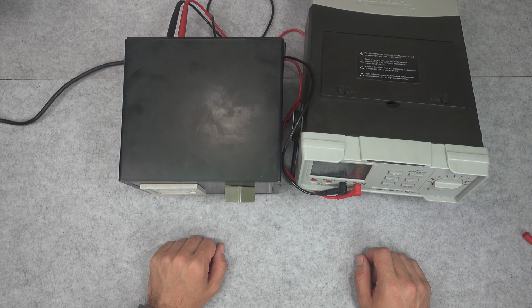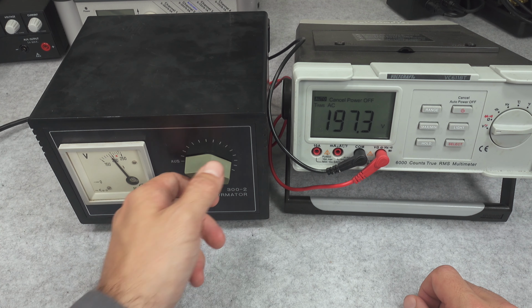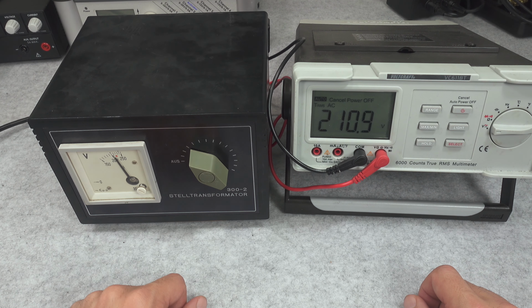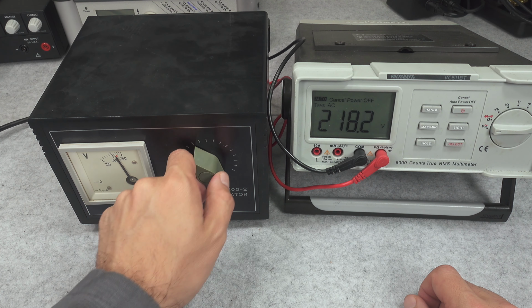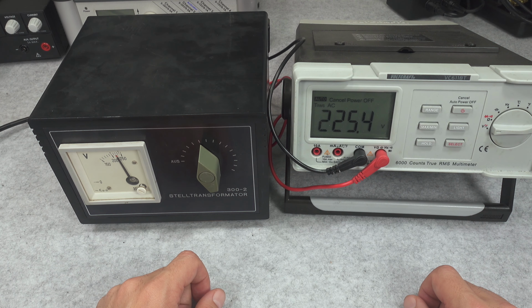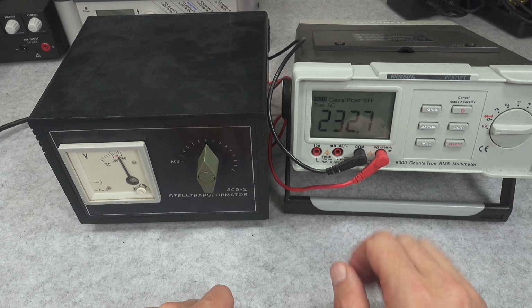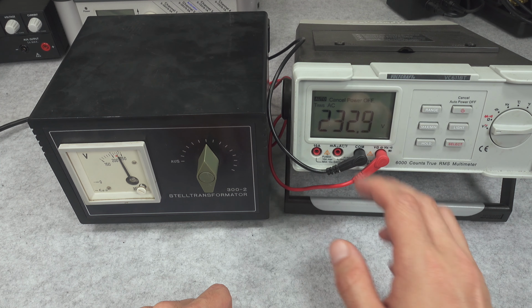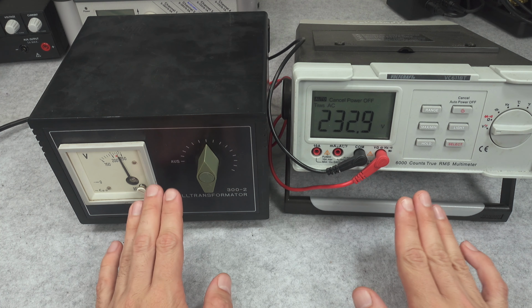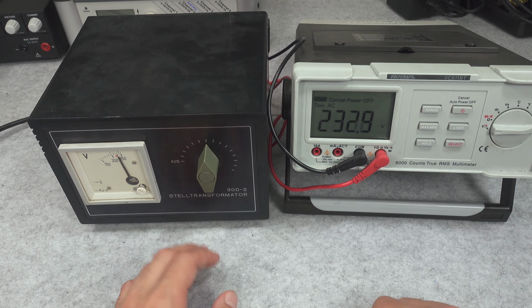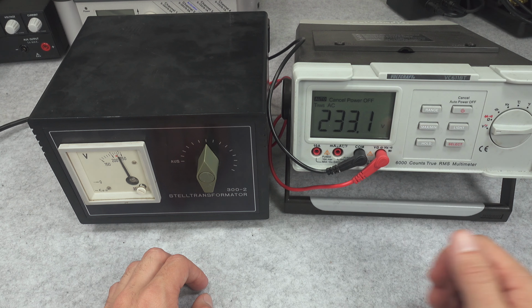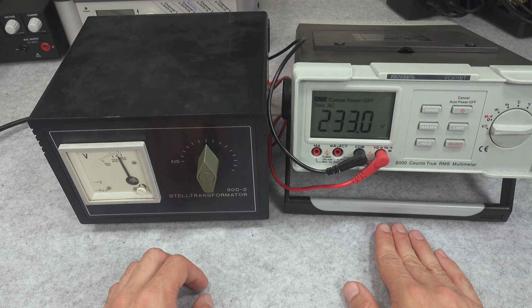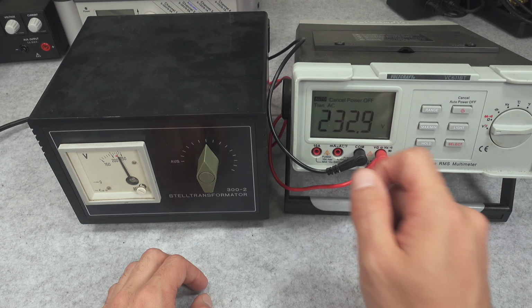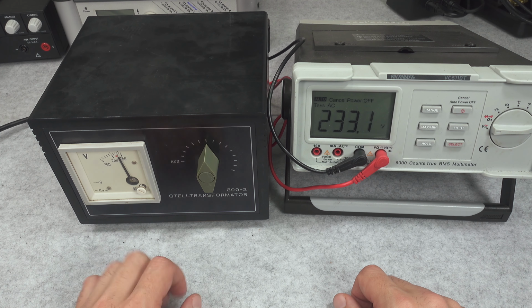Of course, except for testing safety features, this can be used for testing the efficiency of different power supplies. So we are going to set it to exactly the design voltage, and then we are going to measure the efficiency, and you've got pretty accurate measurements. So as you can see here, if we were in the European Union, we've got 230 volts, and this is going to be our base reference. And just in case someone near us has a PV inverter that is making our voltage higher, then we have the possibility to drag it down and make sure that we are in this area.